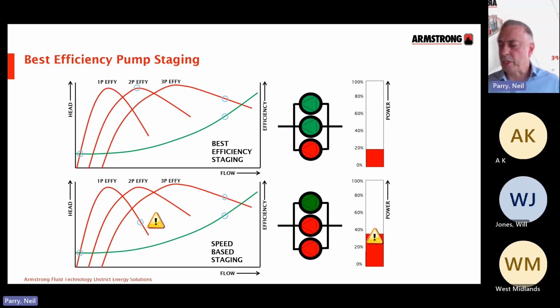There's mention in CP1 about potentially using jockey pumps. My opinion on that is that jockey pumps had their worth if we've oversized everything, so that we have the ability to get down to really low idle flow rates based on what the peak output of that main pump is. But there are problems in moving from a jockey pump onto the system pump, and a big step change in the flow rate and the head that's being produced. Much better to divide that delta between peak and idle between similar sized pumps, and typically 2 would always be the minimum I would look at, and potentially 3 or 4 on big systems, maybe 6 or 8 pumps, to just divide that flow rate up.